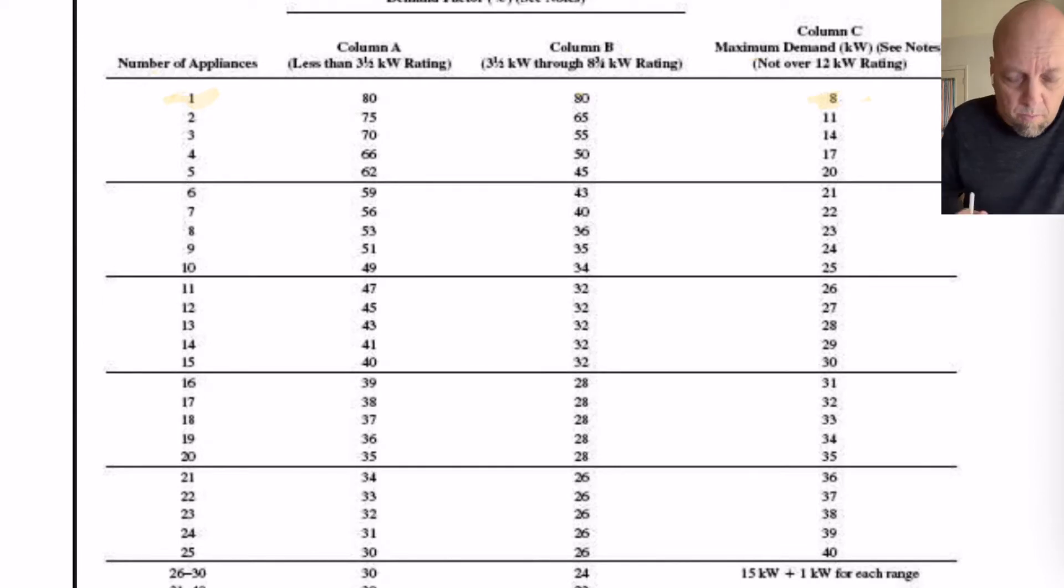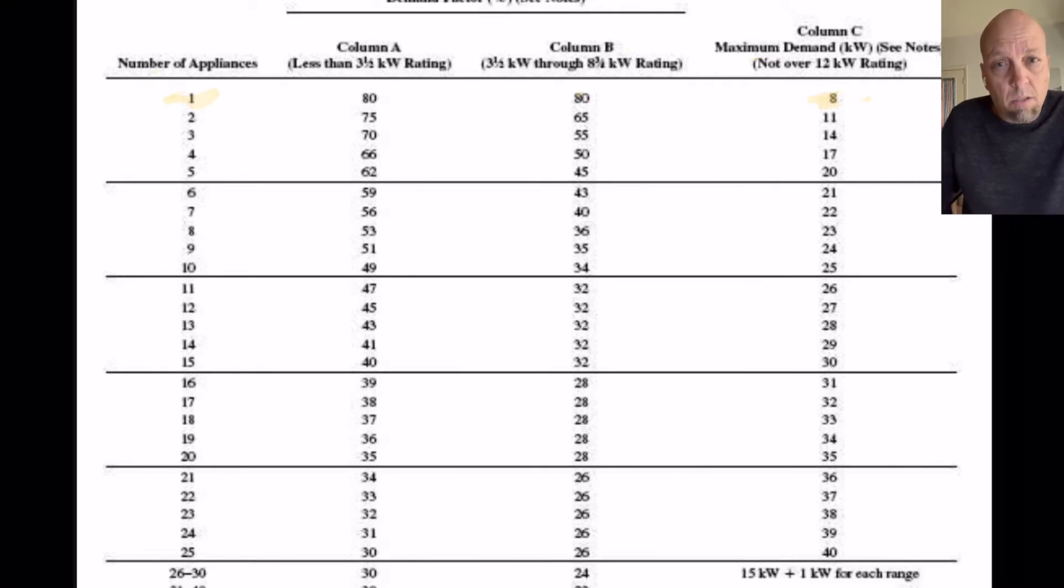But today, remember, we will be in row one because we'll be using one. We'll be figuring out for one load of a range, just one range. And it's not going to be larger than 12kW. So, remember, a 12kW range is actually 8kW. They figured that out for us already. So, let's keep that in mind.